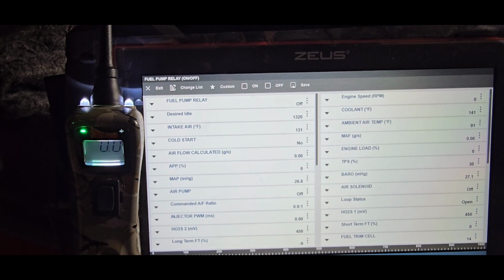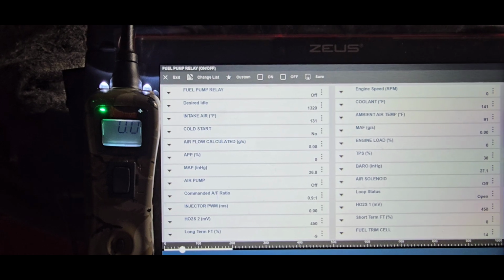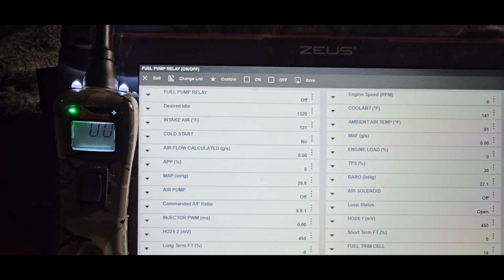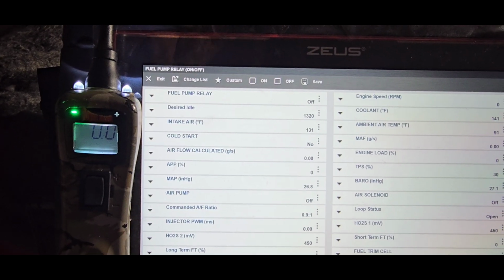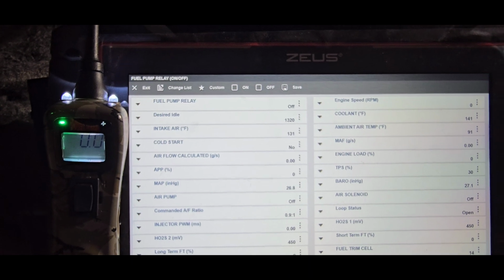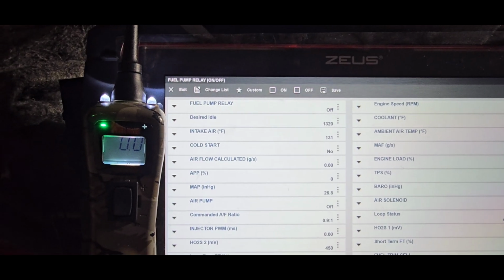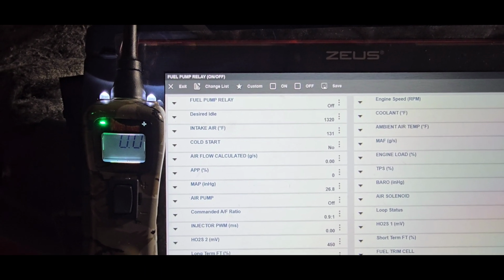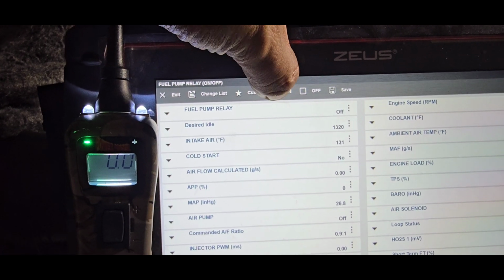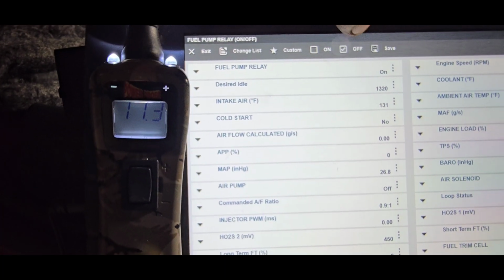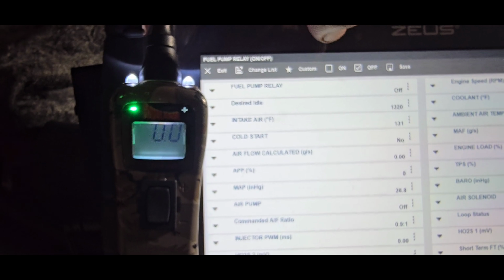All right, so the power probe is connected to the control side. If we energize this relay by selecting on, we are commanding the PCM to energize the relay, and you should be able to see that voltage present. So if we energize the relay now, select on, you can see the voltage; turn it off, voltage goes away.